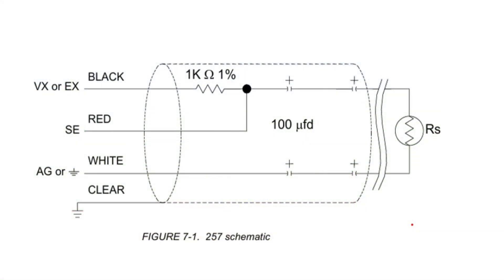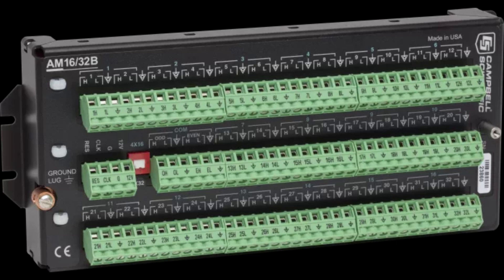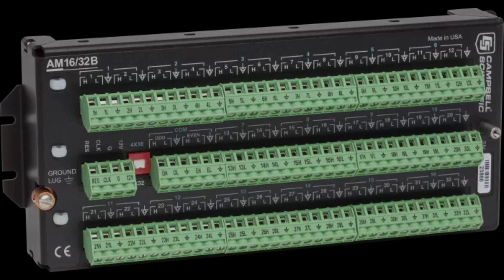Campbell Scientific resistive soil probes and conductivity probes are built with series capacitors to block this kind of ground loop. Resistive sensors without blocking capacitors may be connected to an AM16/32B multiplexer. The mechanical relays in the multiplexer break the connection between the sensor and the data logger between measurements so that no current can flow.